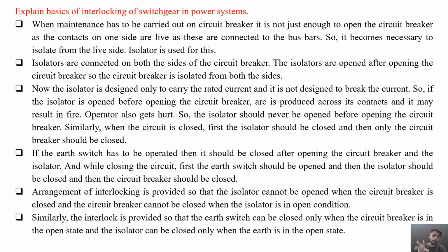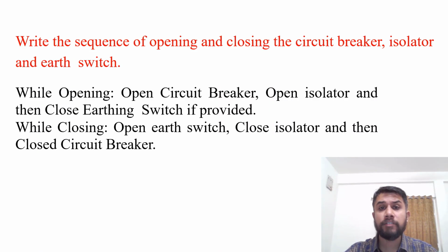Similarly, the interlock is also provided so that the earth switch can be closed only when the circuit breaker is in open condition and the isolator can be closed only when the earth switch is in open condition. So this is the basics of interlocking of switchgear in power system to maintain the system healthy condition and for the maintenance purpose. Sequence of opening and closing the circuit breaker, isolator and earth switch. By opening, first of all, open circuit breaker as it is an on load switch. Then open isolator. So this is an off load switch, and then close earth switch if provided to ground the residual charge available on the poles. While closing, first of all open earth switch, close isolator, and then make the contacts of the circuit breaker.